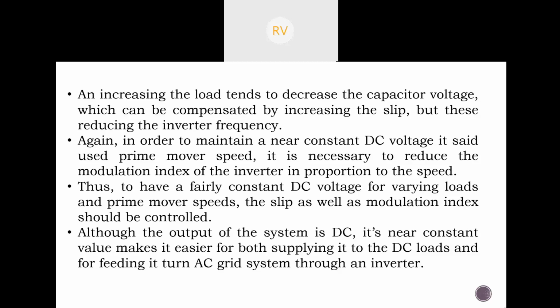An increase in the load tends to decrease the capacitor voltage, which can be compensated by increasing the slip, that is, reducing the inverter frequency. So if the load is increasing, then the capacitor voltage decreases.